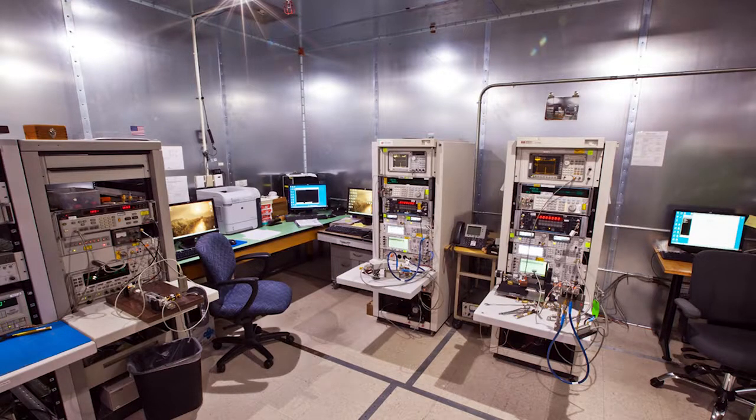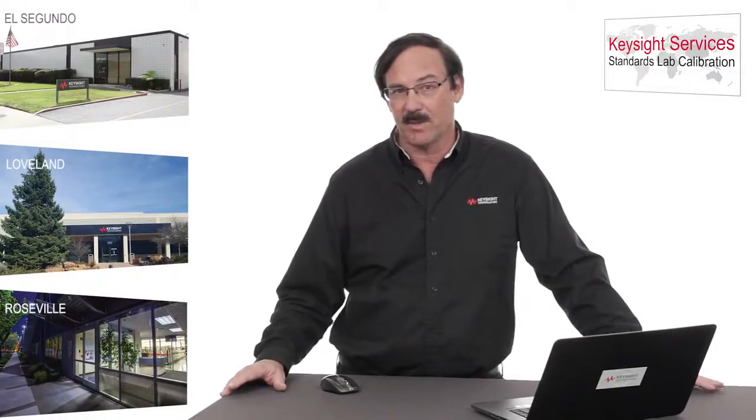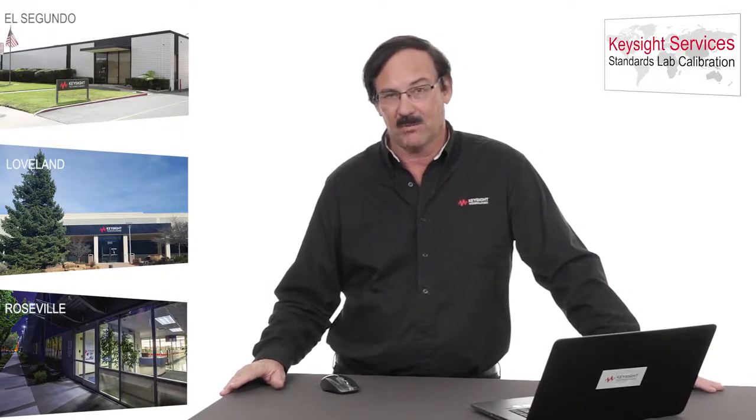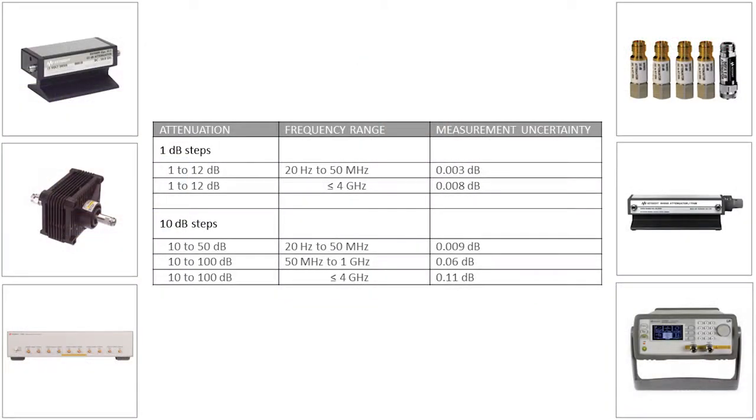This room is completely shielded, and we're able to measure attenuators zero to 120 dB without having to stop and measure individual steps. We have enough dynamic range in this chamber that up to 4 gigahertz, we're able to look at attenuation with an incredible measurement uncertainty down to 120 dB attenuation directly. If you need attenuators calibrated absolutely accurately, I encourage you to consider using the Roseville Standards Lab for those measurements.